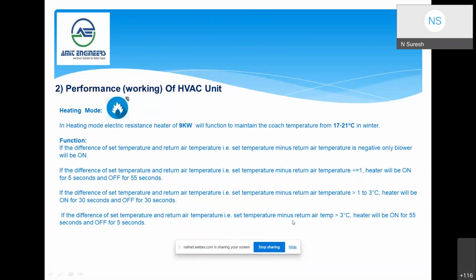In heating mode, there is a 9 kilowatt heater in one unit to maintain the temperature from 17 to 21 degrees in winter conditions. If the set temperature minus return air temperature is less than or equal to 1, the heater will be on for 5 seconds and off for 55 seconds. If the difference is greater than 1 up to 3, the heater will be on for 30 seconds and off for 30 seconds. If the difference is greater than 3 degrees Celsius, the heater will be on for 55 seconds and off for 5 seconds.